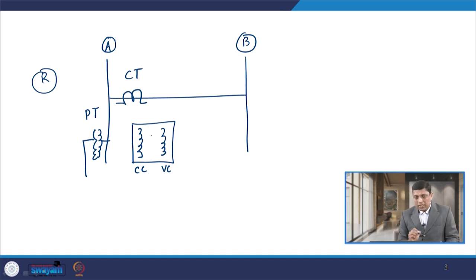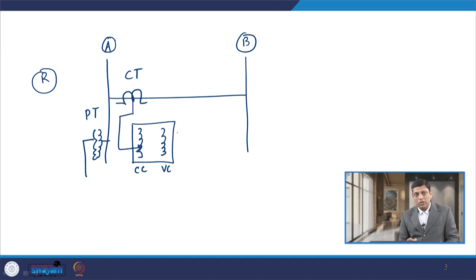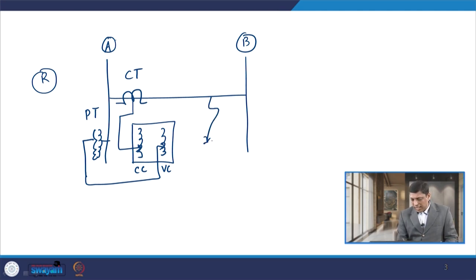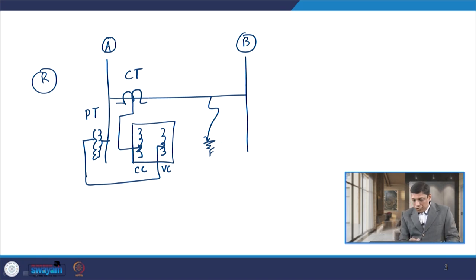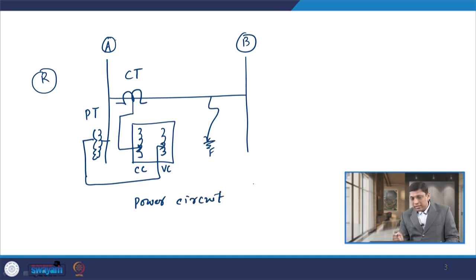The signal to the current coil of the relay is given through the secondary of the CT, whereas the signal to the voltage coil is given through the secondary of the PT. Whenever any abnormal condition or fault occurs on this line, depending upon the magnitude of current and whether the relay is a single input or two input relay, the relay operates and gives signal to the circuit breaker or further auxiliary relay. This circuit is known as the power circuit.